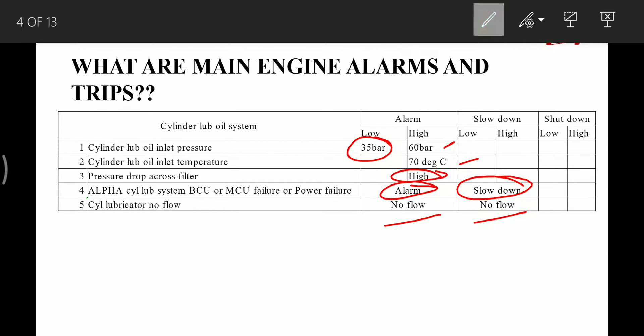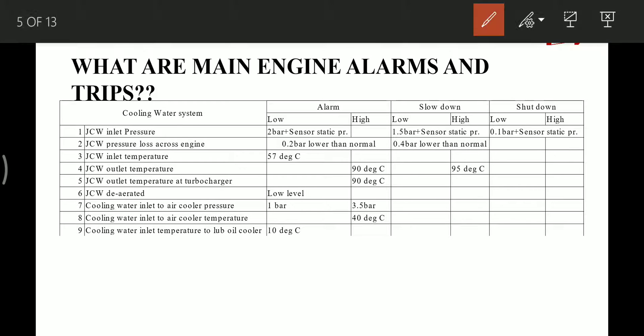Next is the cooling water system. Jacket cooling water inlet pressure: low-low alarm comes at 2 bar plus the sensor static pressure at that pipe location. Slowdown occurs at 1.5 bar plus sensor static pressure, and shutdown at 0.1 bar plus sensor static pressure. This sensor gives alarm, slowdown, and shutdown of the main engine.